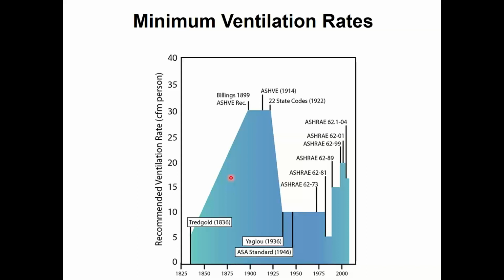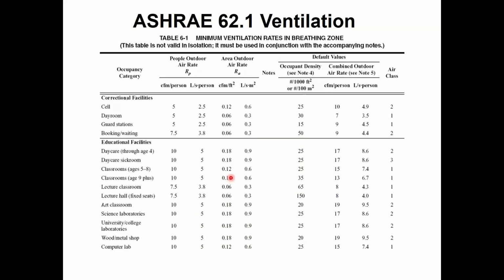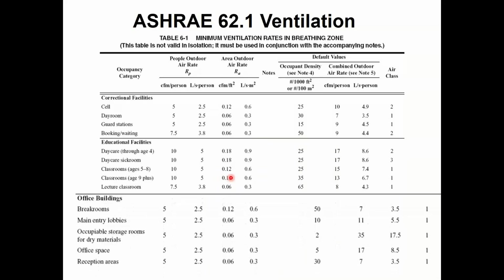So what that does, when that economizer gets the signal for occupancy, is it lowers the minimum damper position from whatever you set it for code compliance, like we talked about with this screen right here last week. It changes it from that down to 0 for the minimum. Then during the daytime, the damper for an economizer mode can modulate between minimum and 100%. At nighttime, it can modulate between 0 and 100%.